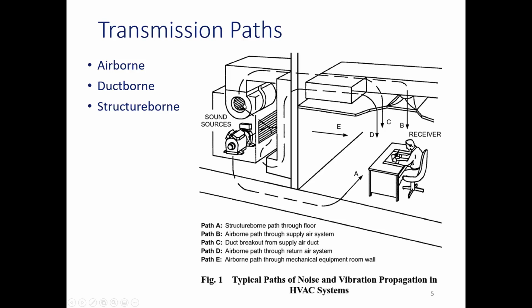The airborne path is just these producing noise, coming out through this louver, and that sound is transmitted through the wall - that'd be those noise reduction calculations we just did. That's the airborne path, like casing radiated. You don't have to have that louver; you might just have a casing over it. When you have a louver, air needs to be brought in for cooling or taken out for exhaust. But some units are just a casing over them, not having outside air or exhaust, and that casing radiated would be airborne.